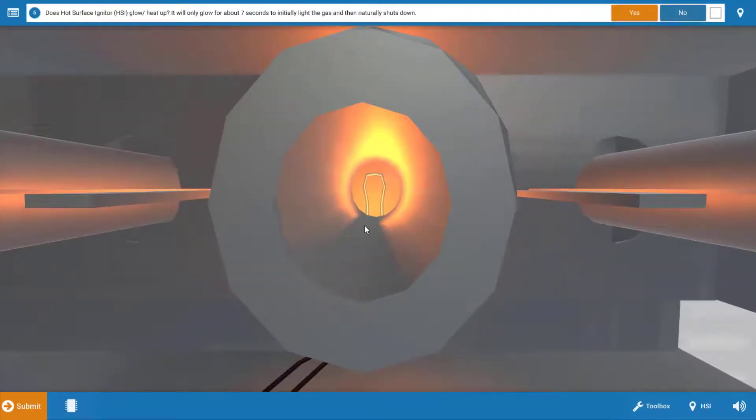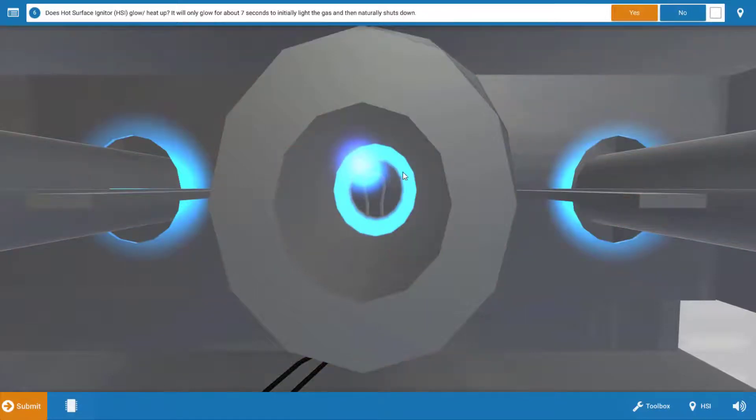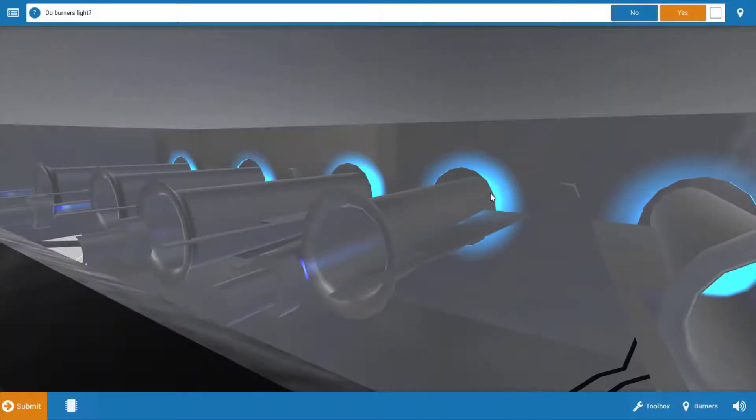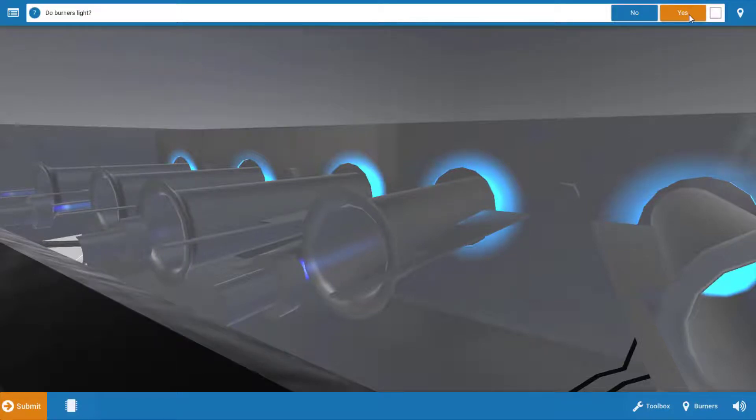To start with, the igniter glows. We can see the glow from the igniter. This will glow at around 2600 degrees or so, so it's going to be obvious if it's working or not. So we're going to click yes. Next, the burners. The burners do in fact light off, we can see we have burner ignition, so we're going to click yes.